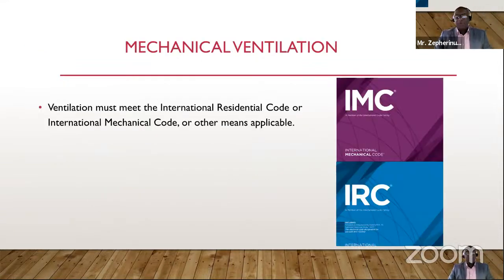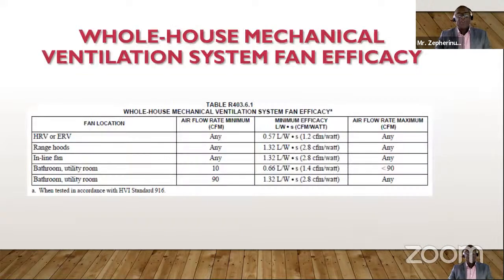Mechanical ventilation, very, very important. It is a mandatory requirement, and there are requirements, as I said, for the fans, the number of air changes, and how buildings are ventilated, referencing other international codes. So there are a suite of codes and standards that the CREEBC references to bring to you the best available, best practices to see after the energy efficiency of your buildings, and of course, the safety of the occupants. So if you're doing a whole house mechanical ventilation, you have to consider the efficacy of the fans, and the efficacy of the fans depending on the location of the fan.